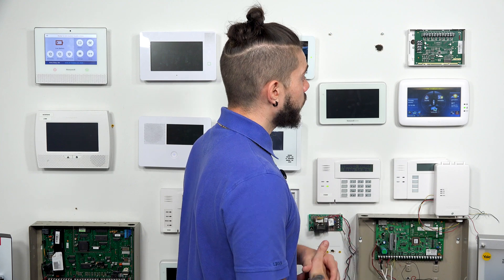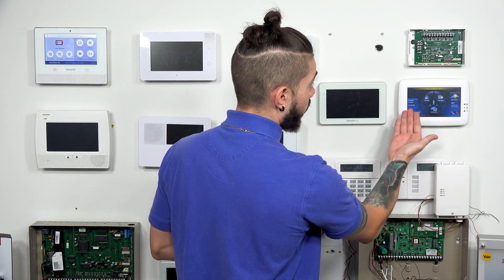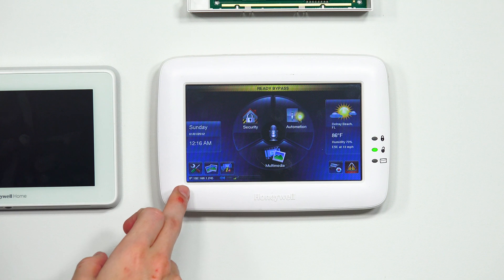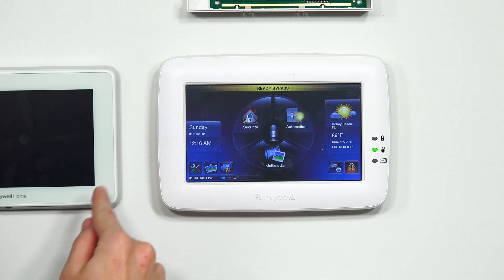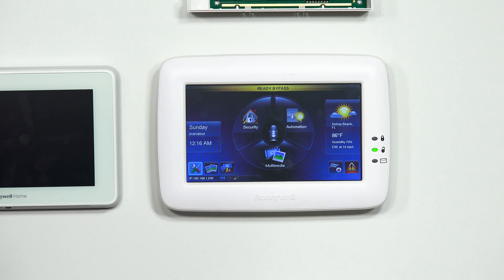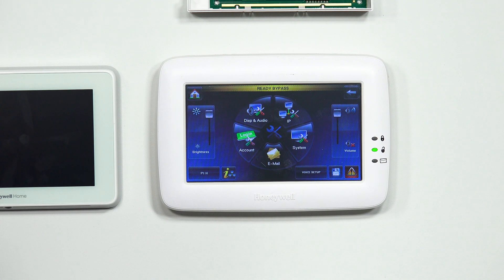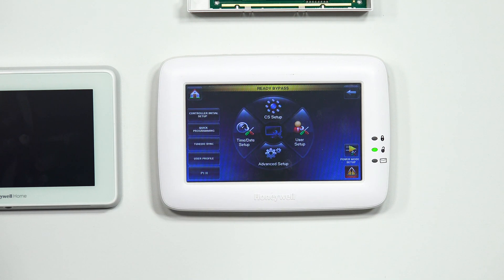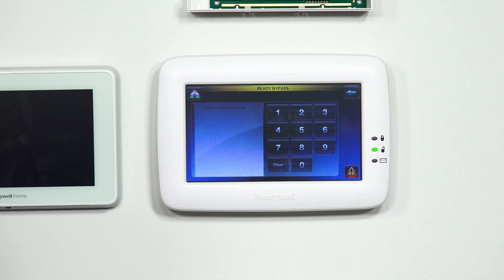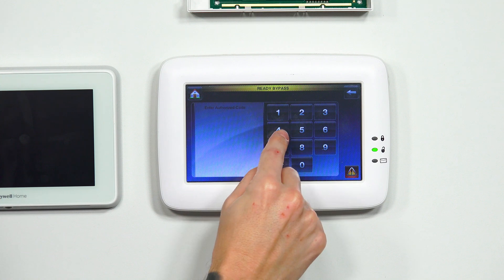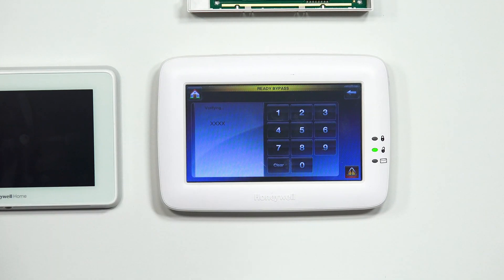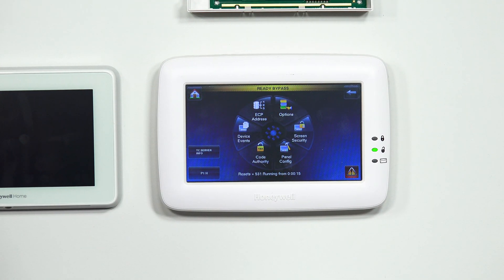The first thing we have to do is, on the bottom left-hand corner from the main screen, there's going to be a little screwdriver and wrench icon — that's the Settings or Tools. We're going to hit the Tools icon in the bottom left corner. From there, we're going to go to System, then CS Setup. Here's where it's going to ask you for your installer code. I'm going to enter in 4112. From there, the ECP address is one of the first options you'll see, so you go to ECP address.